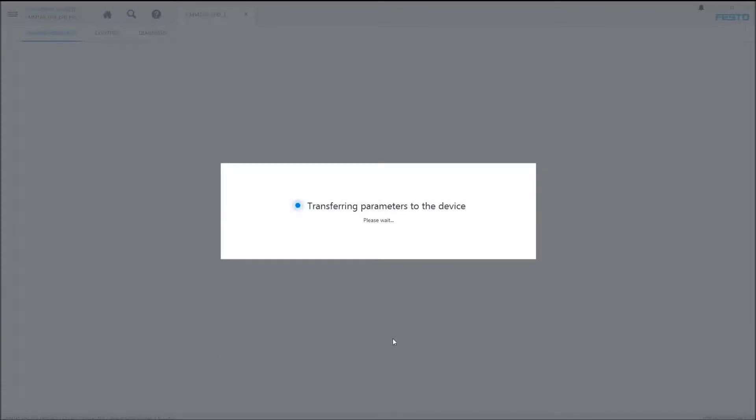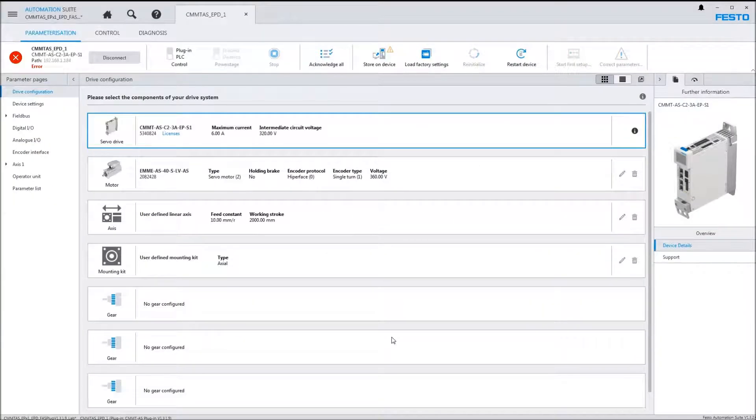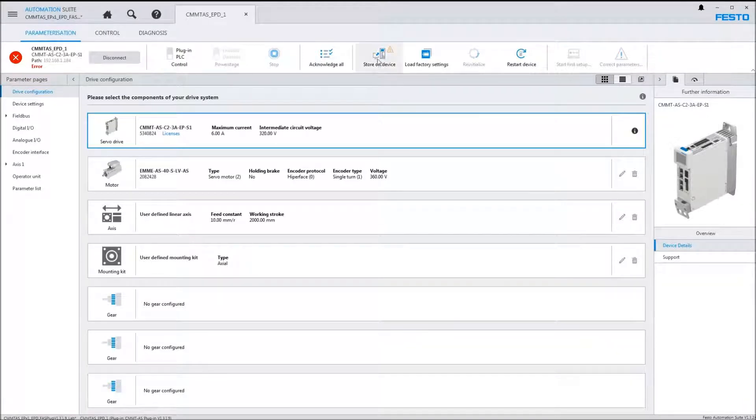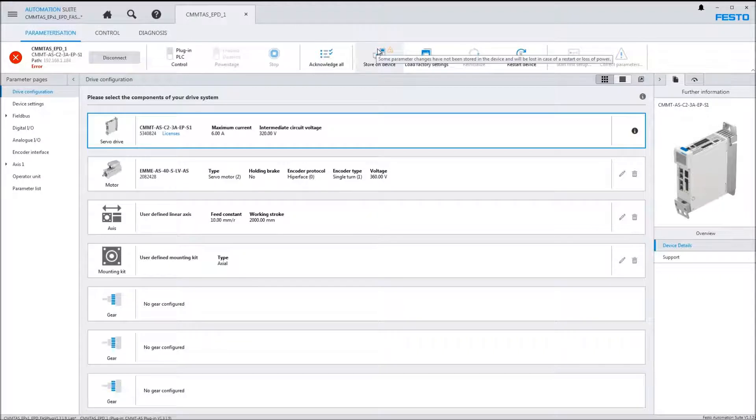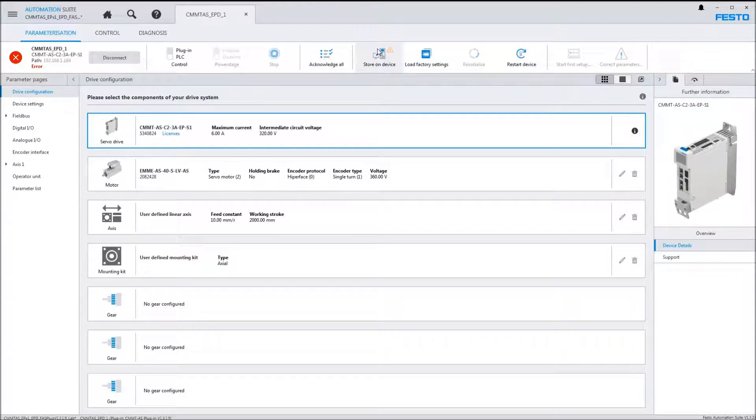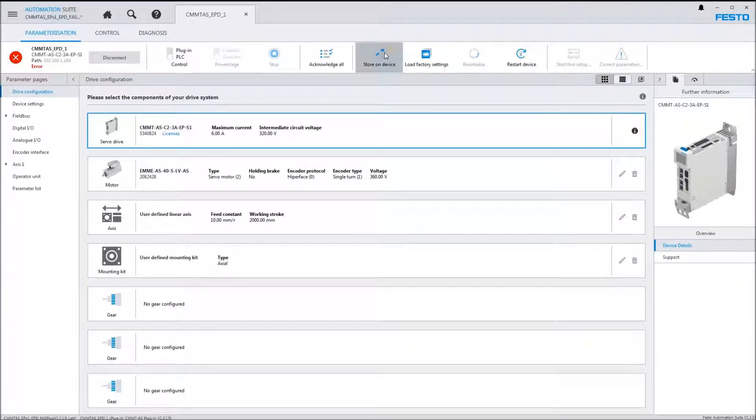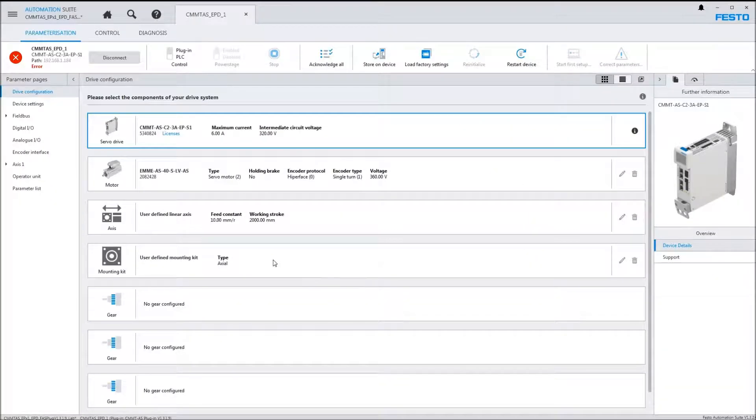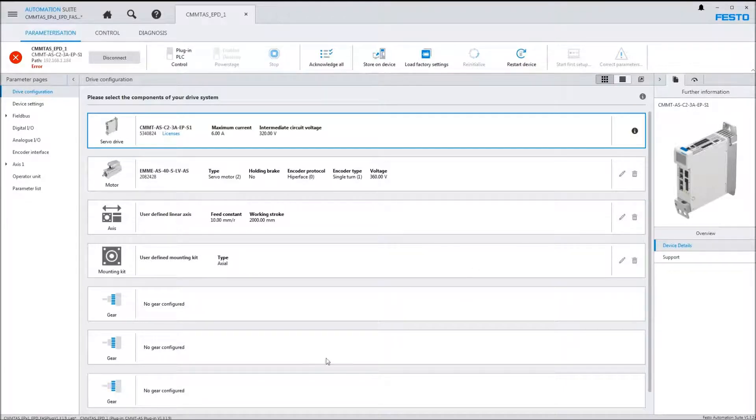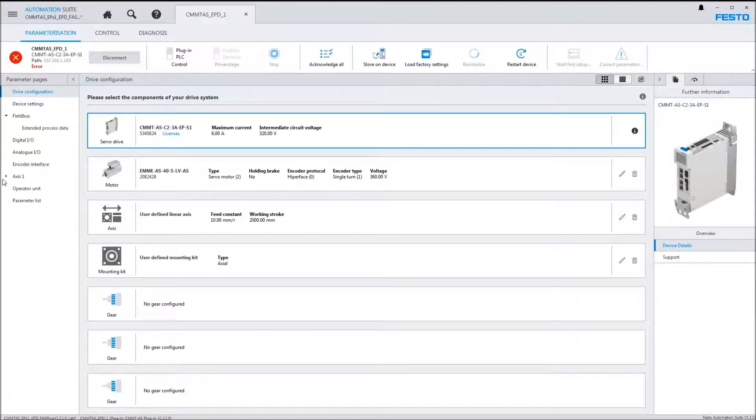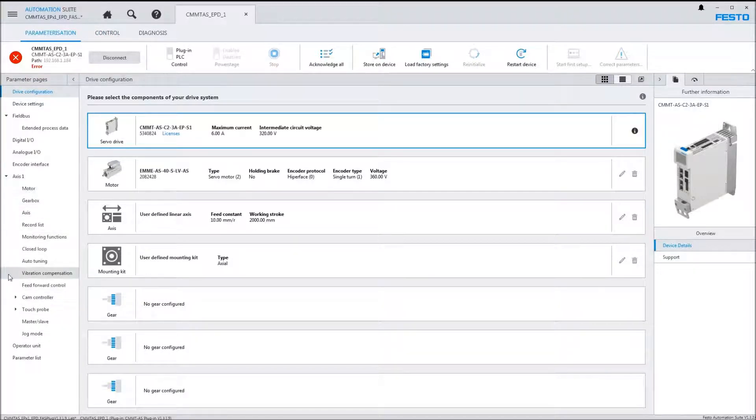I'm going to write to the device, and now we're online. We put this into the volatile memory, so if we did a cycle of power on the controller, we would lose that data. The next step logically is to do the store on device. Click on that to store that information on the EPROM.